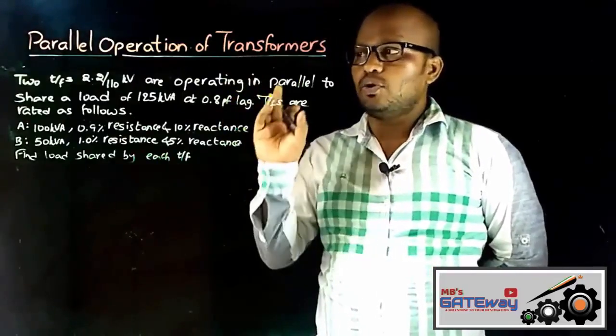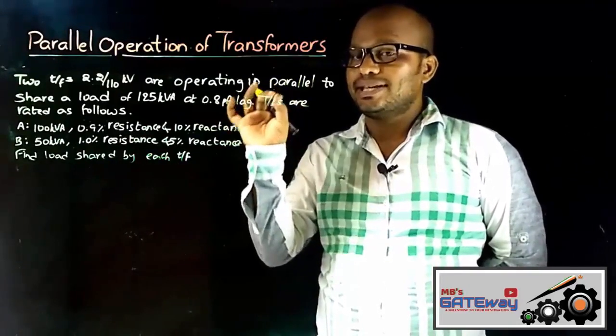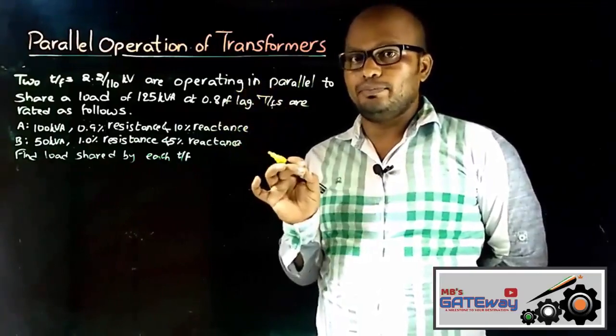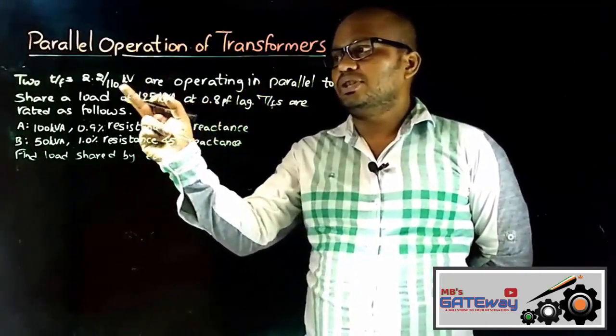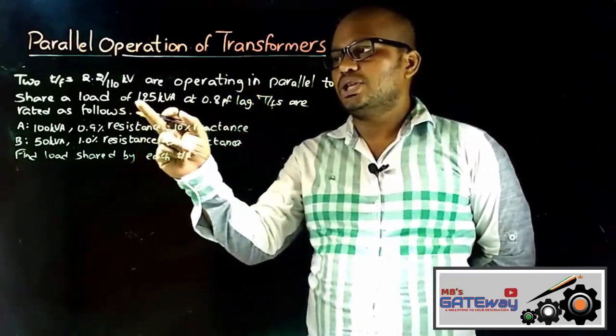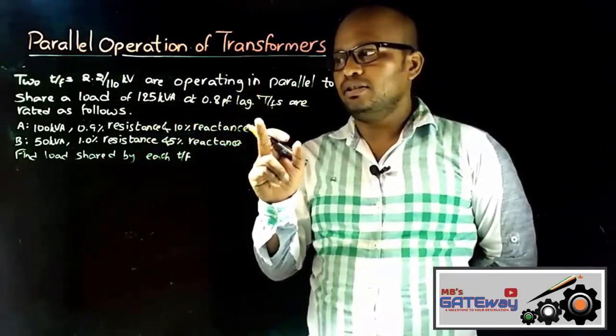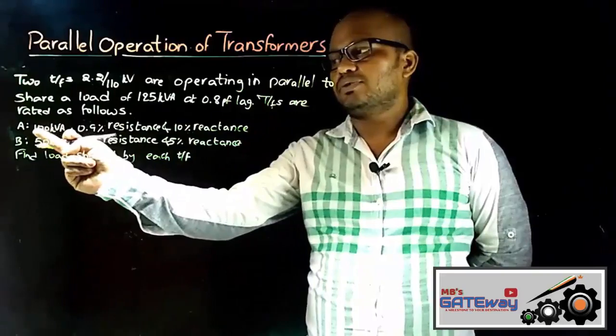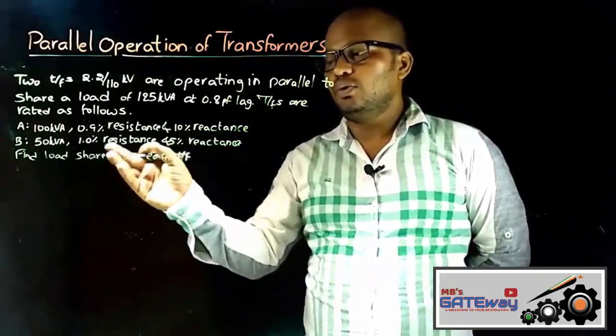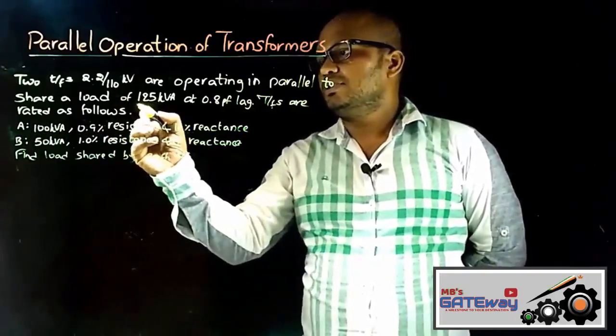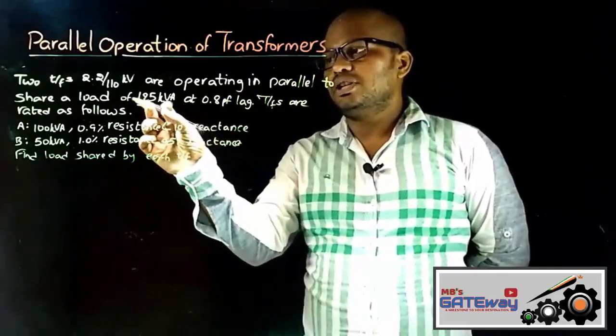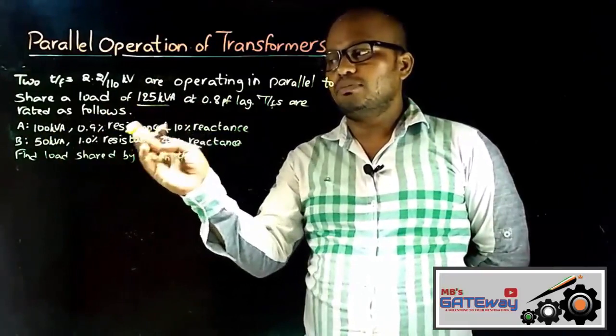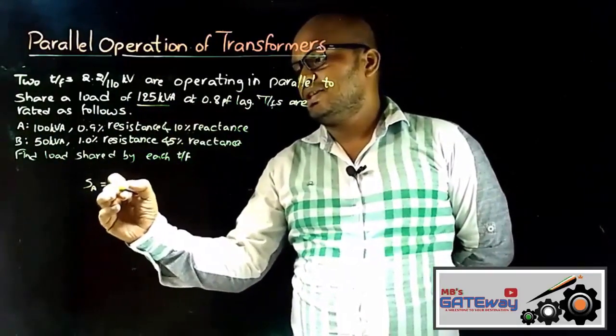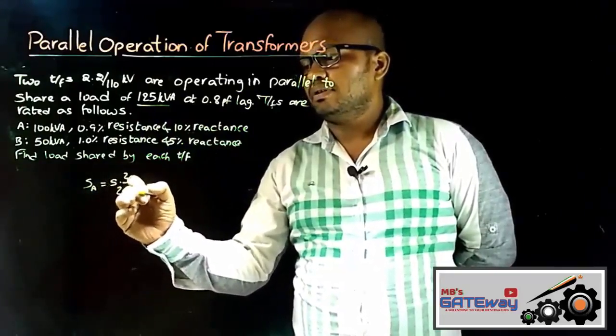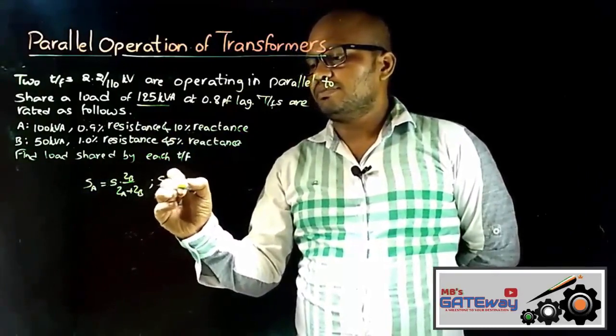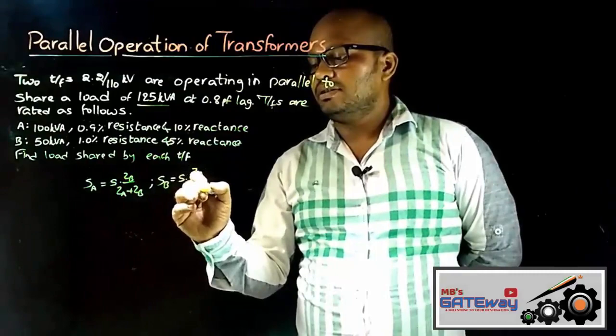Now, before ending the discussion on parallel operation of transformers, it is very essential to discuss an important concept that will make us able to solve the numerical problem. So this is the numerical example in which there are two transformers operating in parallel, and they have to share a load of 125 kVA at 0.8 power factor lagging, and these are the corresponding values of transformer A and transformer B, and we need to find the load shared by each transformer. So this is the load, and we need to find the load shared by transformer A and transformer B. We have SA is equal to S into ZB by ZA plus ZB, and SB is equal to S into ZA by ZA plus ZB.